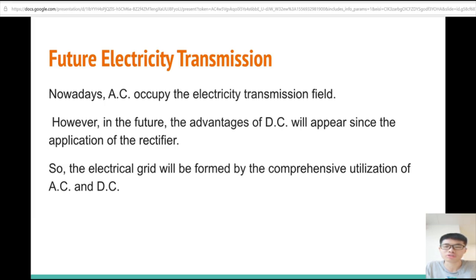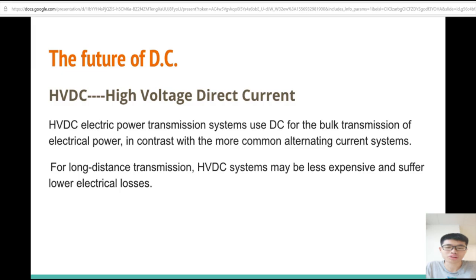HVDC electric power transmission system uses DC for the bulk transmission of electrical power in contrast with the more common alternating current system. For long-distance transmission, HVDC systems may be less expensive and suffer lower electrical losses. A comprehensive HVDC system includes the conversion system, transmission system, and connection system. Conversion system has two major equipments, including the converter and converter transformer. Converter transformer changes the voltage of AC to a certain voltage that can be used by the converter, and the converter changes AC to DC.